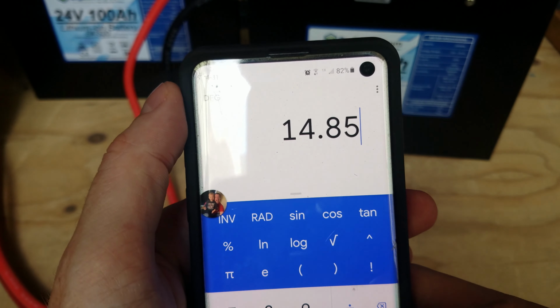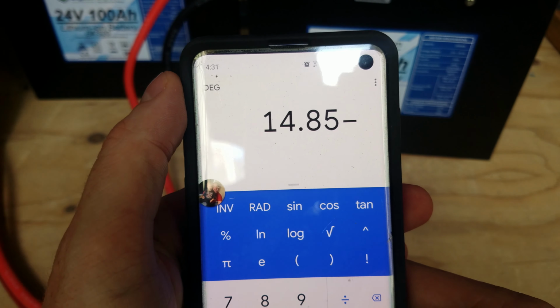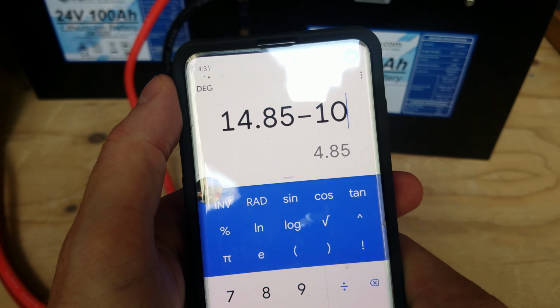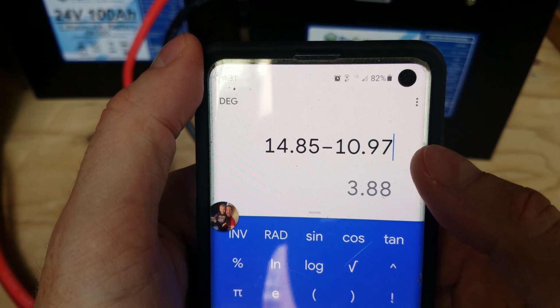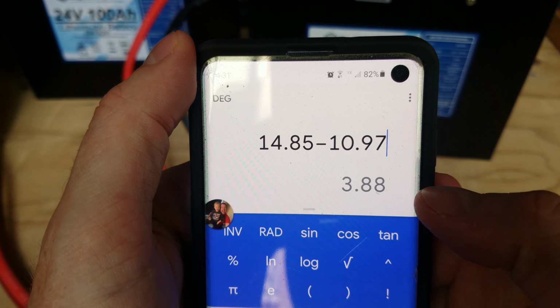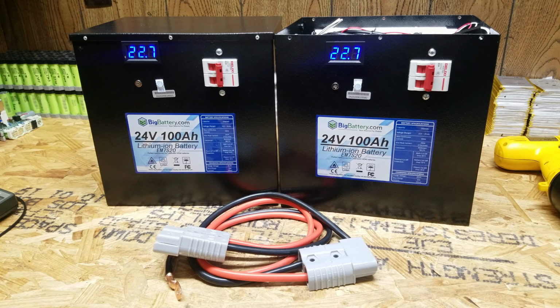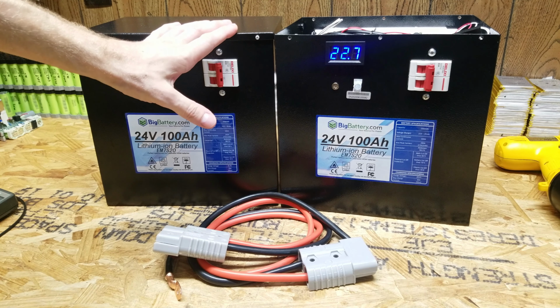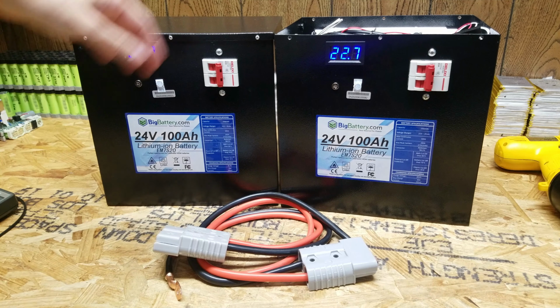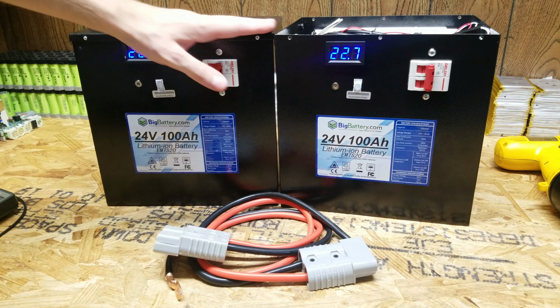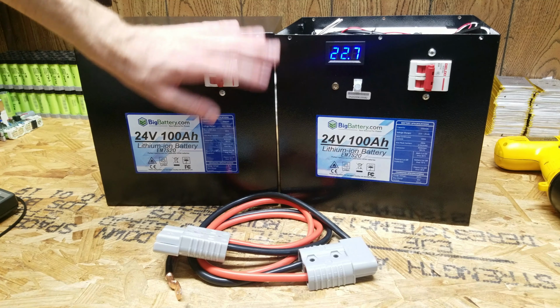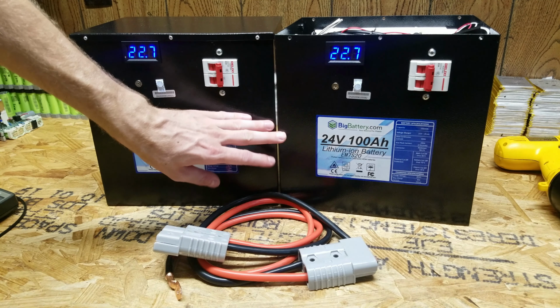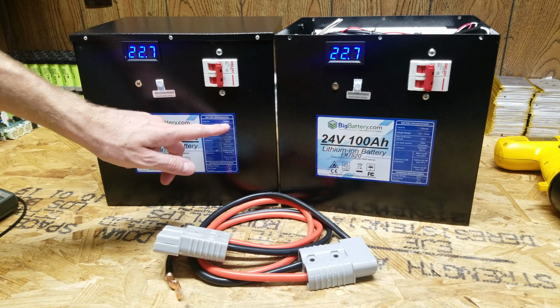14.85 kilowatt hours minus, we started our test at 10.97, and that gives us 3.88 kilowatt hours of power. Alright guys, so I do think that was a pretty thorough test of these batteries. They finished out at 3.88 kilowatt hours between the two of them, and that comes out to 1.94 kilowatt hours per box. They are rated for 2.5 kilowatt hours.